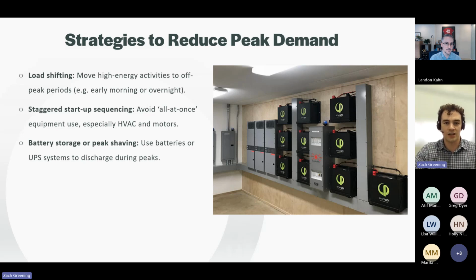The second strategy is to stagger your startup sequencing. Facility teams and staff come in the morning and turn on everything all at once, which can also create a demand peak. Instead, you want to stagger your startup of equipment, especially things like HVAC pumps or lifts, to help flatten out that load curve. This can be automated by your building management system, or implemented manually by your facility teams depending on what level of control you have.